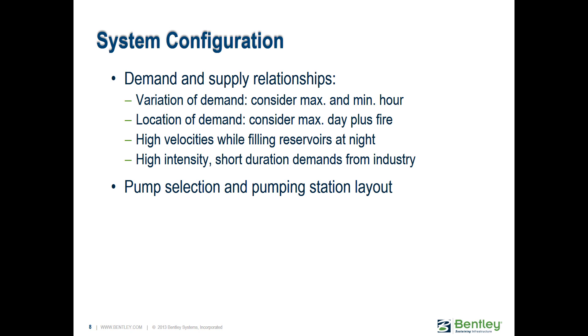Regarding system configuration and demand-supply relationships, a key question is what type of demands to use for a transient simulation. You should consider both the maximum and minimum hour. During high demand periods, velocities tend to be higher and pressures lower, increasing the potential for sub-atmospheric pressure and higher momentum. During low demand periods, higher pressures mean a potential for higher maximum transient pressures. For that reason, it's a good idea to check both conditions.